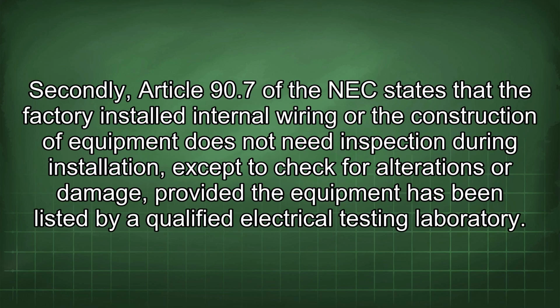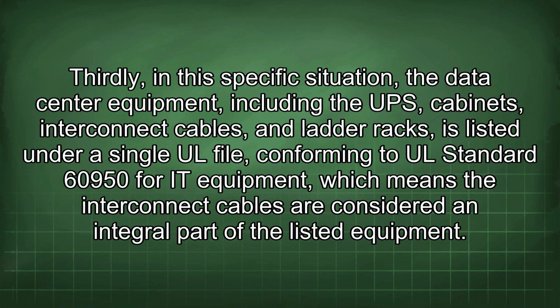Secondly, Article 90.7 of the NEC states that the factory installed internal wiring or the construction of equipment does not need inspection during installation except to check for alterations or damage, provided the equipment has been listed by a qualified electrical testing laboratory. Thirdly, in this specific situation, the data center equipment, including the UPS, cabinets, interconnect cables, and ladder racks, is listed under a single UL file conforming to UL standard 60950 for IT equipment, which means the interconnect cables are considered an integral part of the listed equipment.